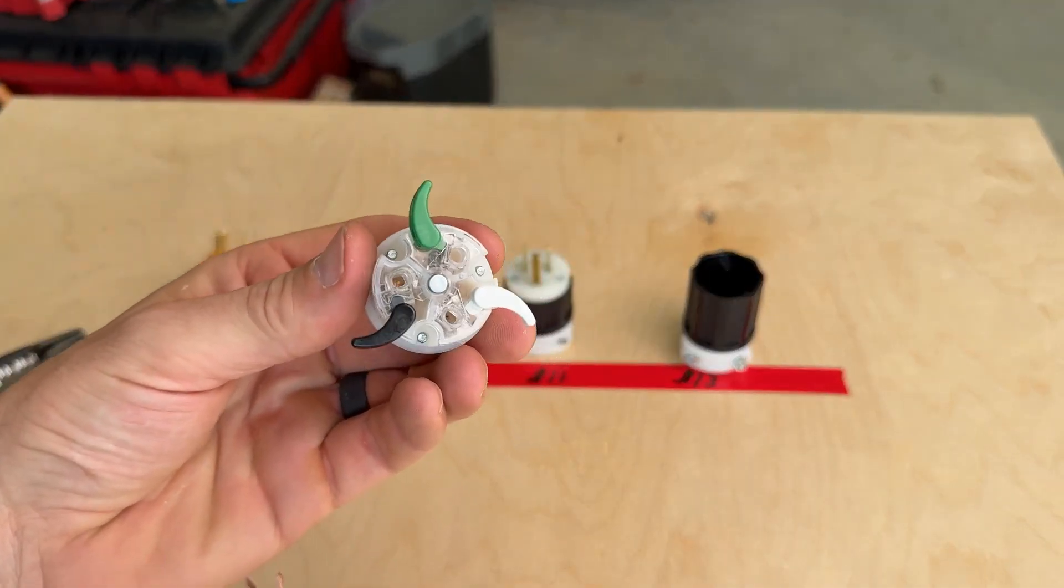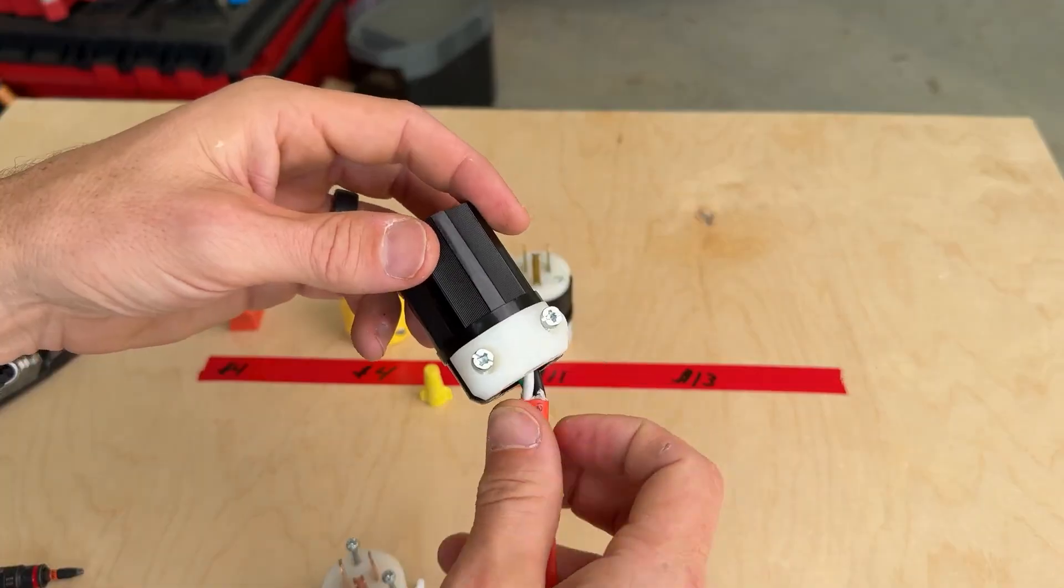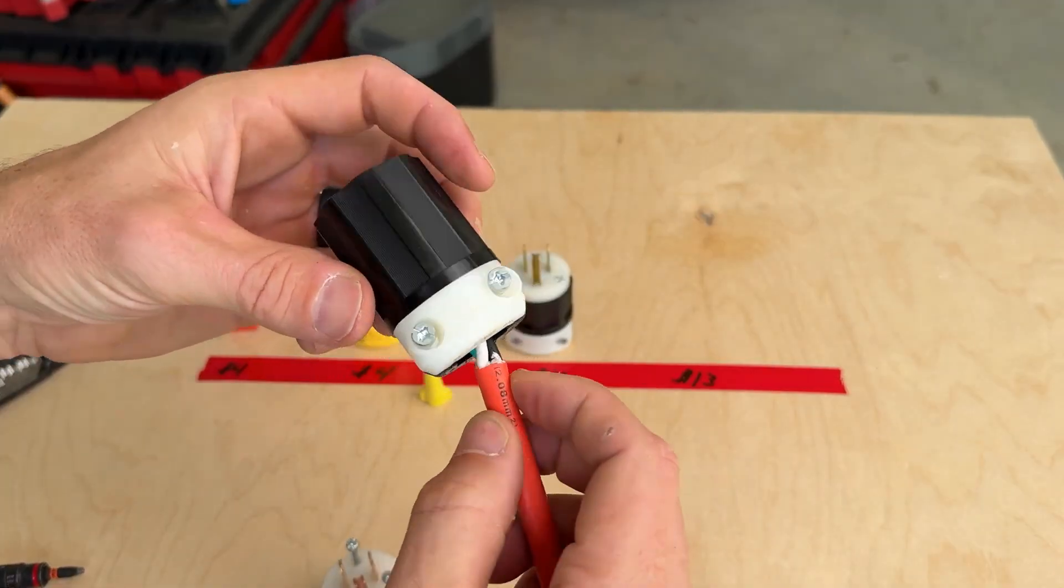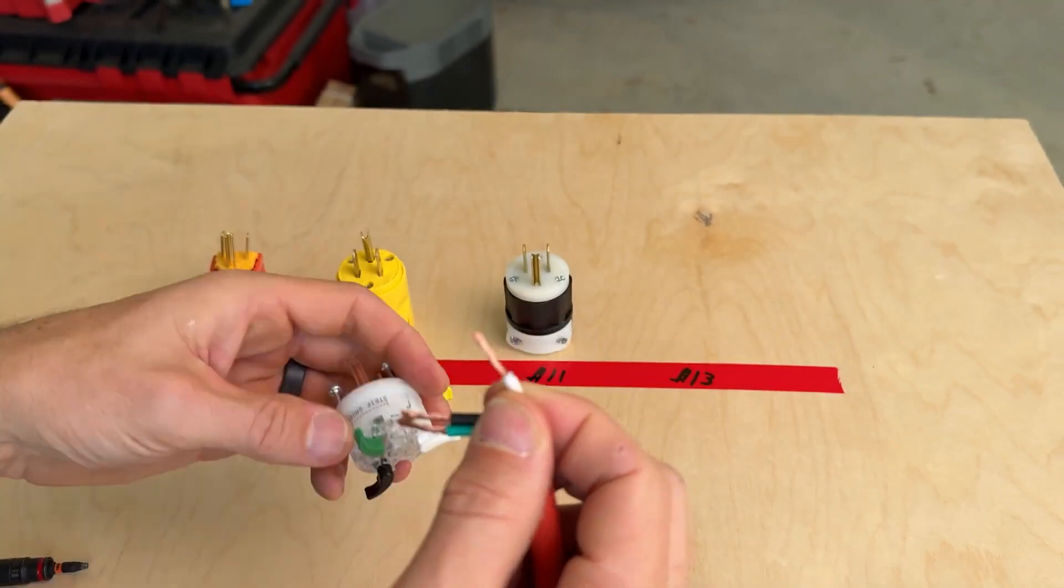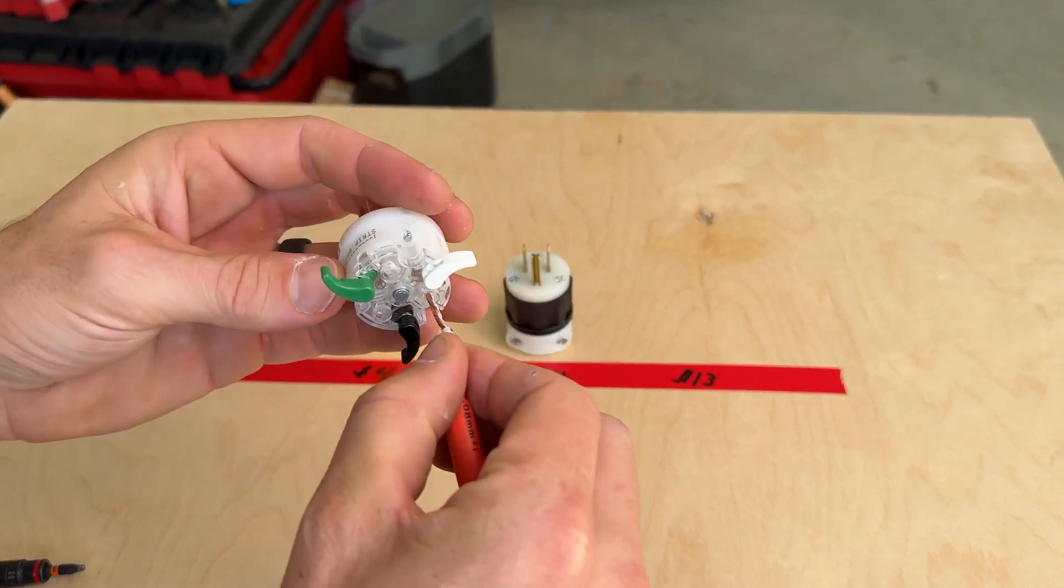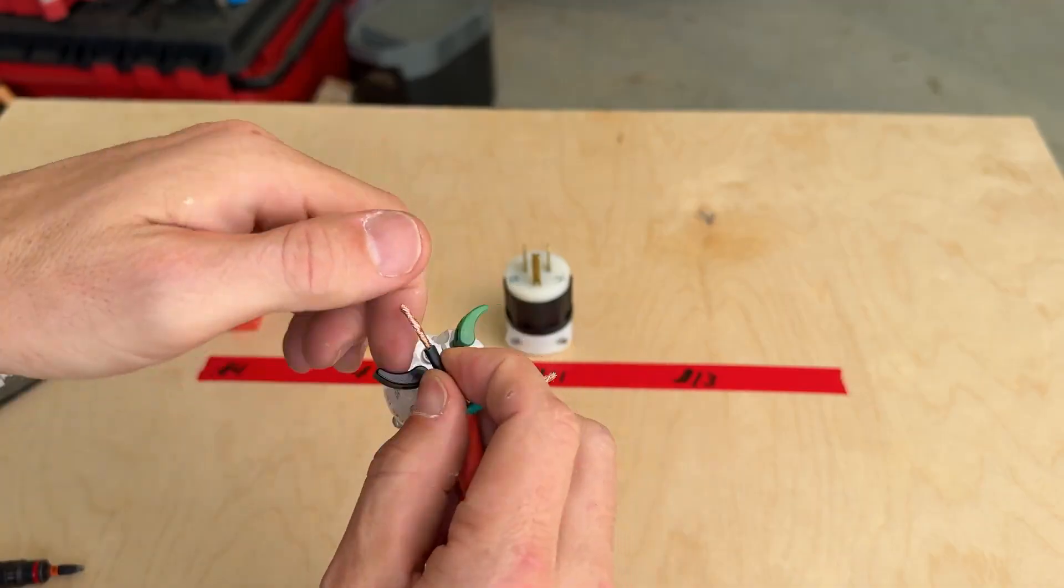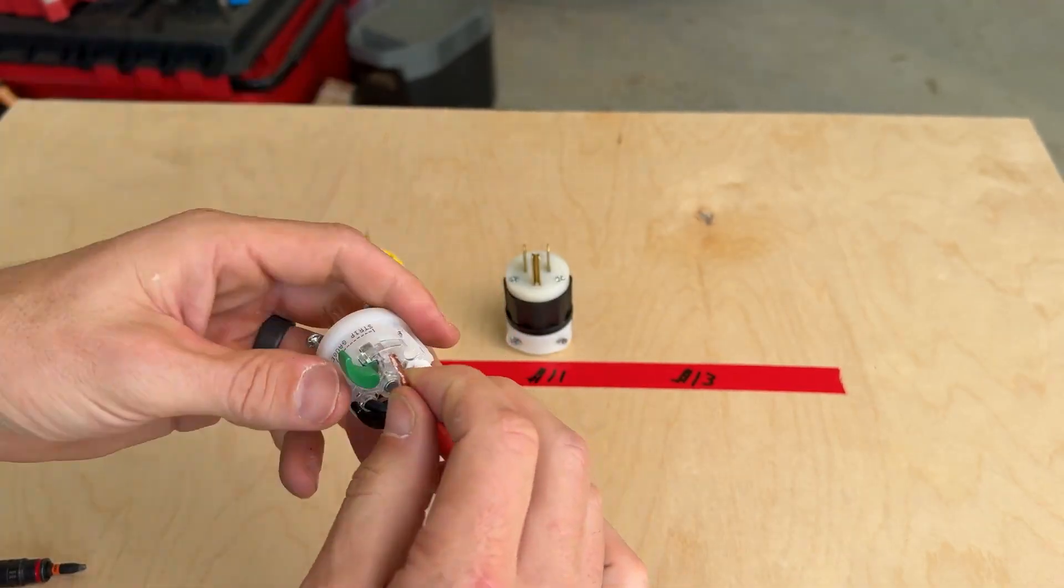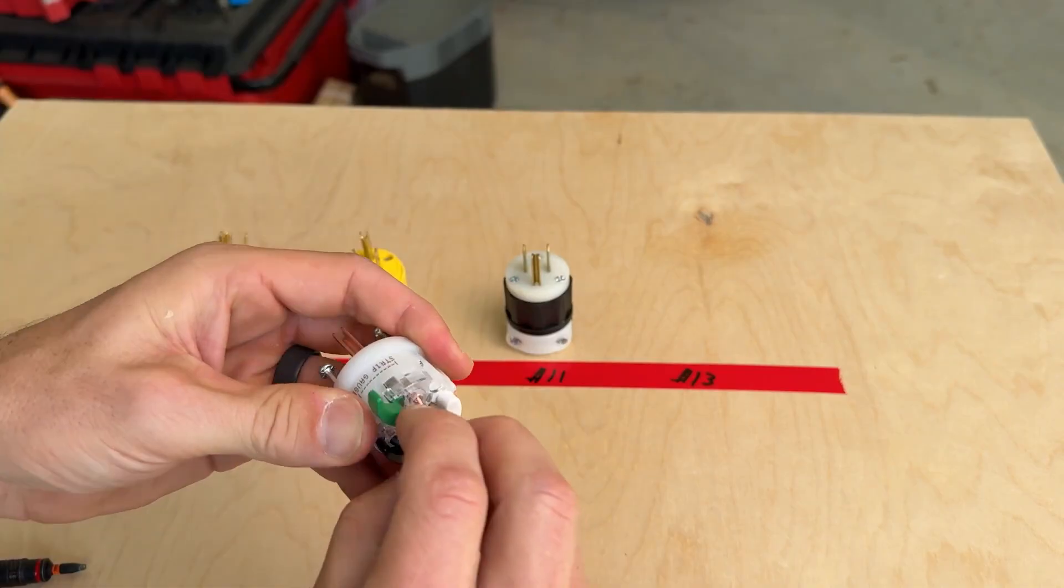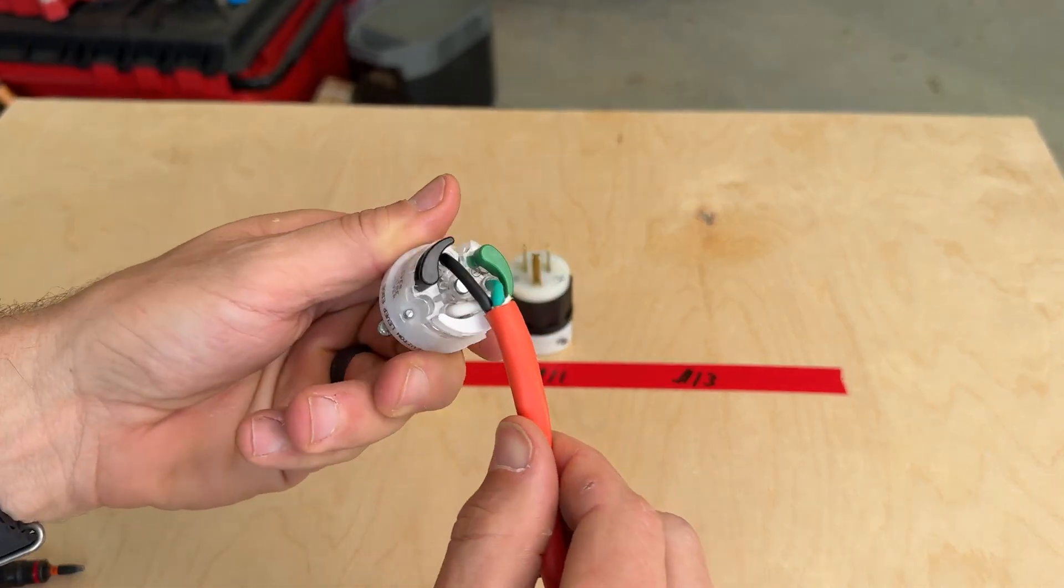All you got to do is pass your wire through your housing. Make sure your stranded wire is twisted, and then you can start landing white on white, your black hot, and then you're just closing down those levers. That is what is making your secure connection. There's no exposed copper in there.